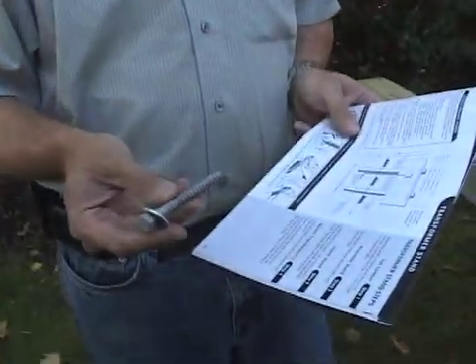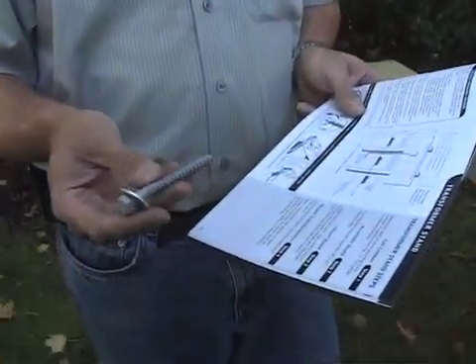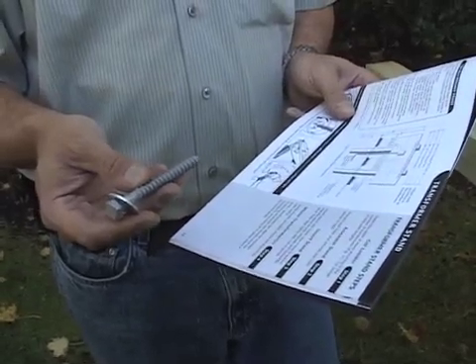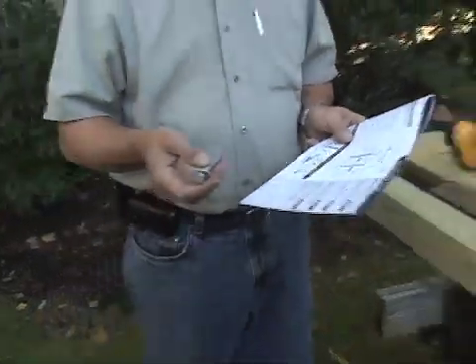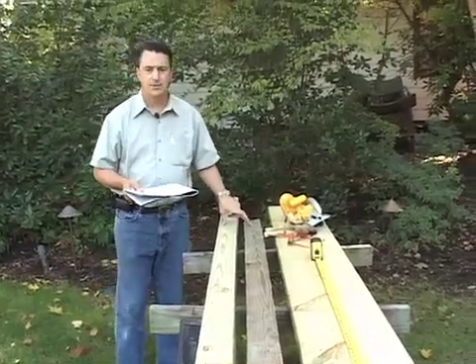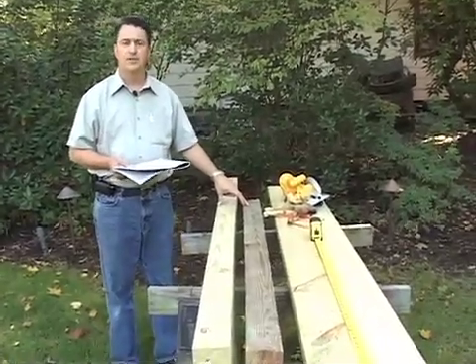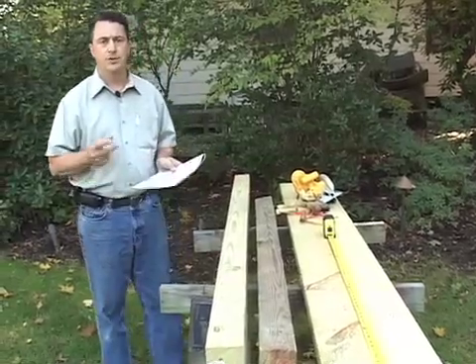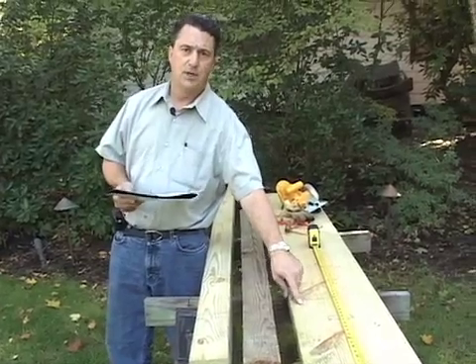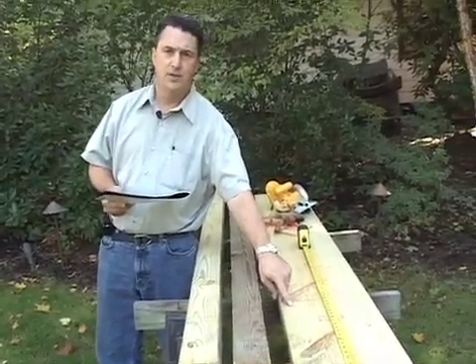Let's go over the materials you're going to need to accomplish this task. First off, you're going to need eight 2½-inch, ⅜ galvanized lag bolts, and with that you're going to need eight ⅜ washers. Now let's talk about the lumber. We use pressure-treated lumber. You're going to need two sections, four by four, that are 68 inches long. And because we're mounting two transformers, we need two sections 24 inches long of 1 by 12 inch pressure-treated lumber.